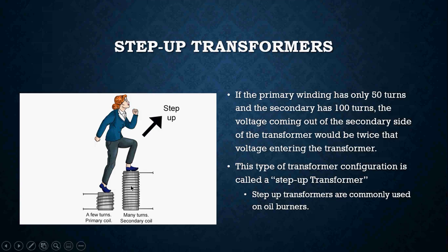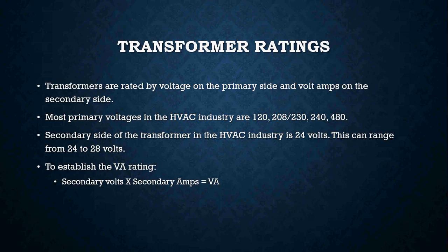Remember those two principles that a transformer works off of: it depends on the amount of electricity coming into it, but it also depends on the number of windings each coil has. Transformers are rated by voltage on the primary side and volt amps on the secondary side. The primary voltages you'll run into in HVAC are typically 120, 208, 230, 240, and 480 volts.